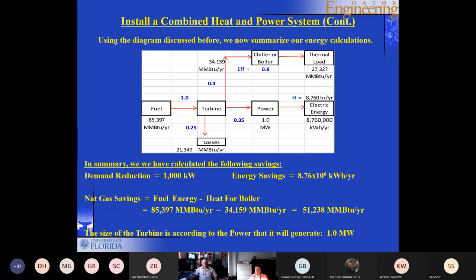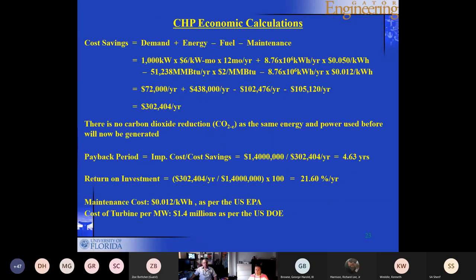The size of the turbine, in accordance, therefore, is going to be able to generate 1 megawatt. You're going to have to buy a 1 megawatt turbine, and it's going to cost you $1.4 million per megawatt. So if you have a 1 megawatt turbine, you're going to need to spend $1.4 million. It's pretty expensive, and many facilities shy away from doing it. But the cost savings are going to be the demand savings plus the energy savings minus the fuel, minus the maintenance.